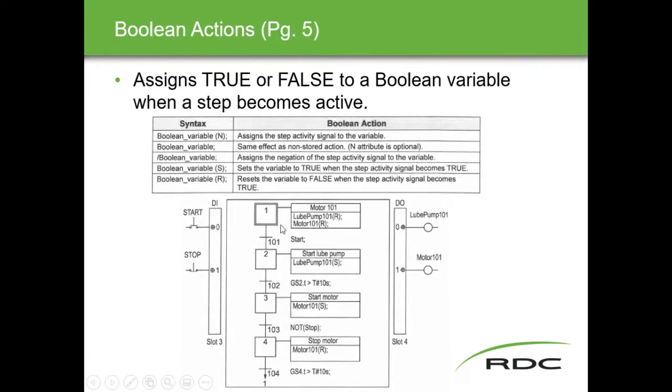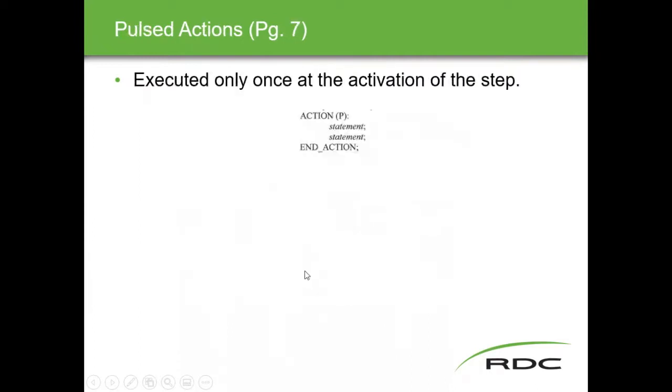When we look at some of the programs here in SFC, remember that this is a relationship to the same program that we looked at in different languages here. So here you'll notice we have a lube pump and a motor and a stop motor button. So this is a classic stop-start scenario where we have a motor and a lube pump that either has to pre-lube for a little while before the motor starts, and then often will stay running for a little while after the motor stops. So again, if you can understand the process through another language, it helps you interpret what's going on in the new language. So we'll see some things that you might recognize from different languages, such as setting the timer.